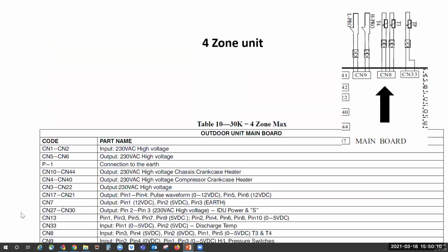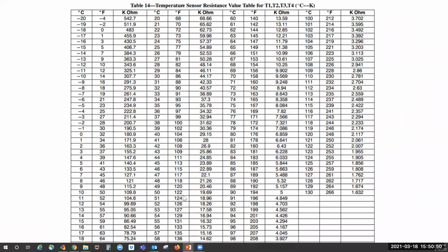Here you're going to be wanting to check voltage. You're going to refer to your table in the service manual. And as you can see here on CN33 and CN8, these are both thermistors, and you're going to be looking for roughly 5 volts DC. Now on CN9, those are switches, high, low pressure switch. So you'll check those like you do any other switch. Are they open? Are they closed? You'll refer to your ohm chart, your resistance chart. Make sure your temperatures and everything match.